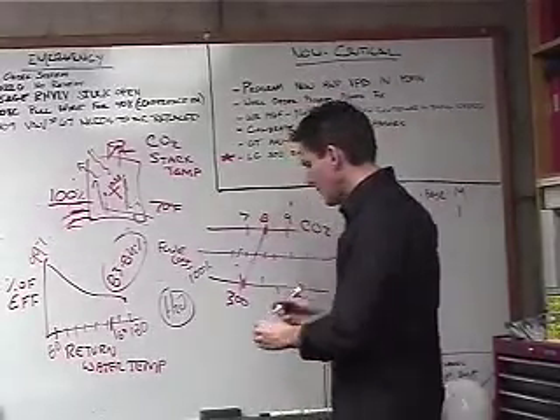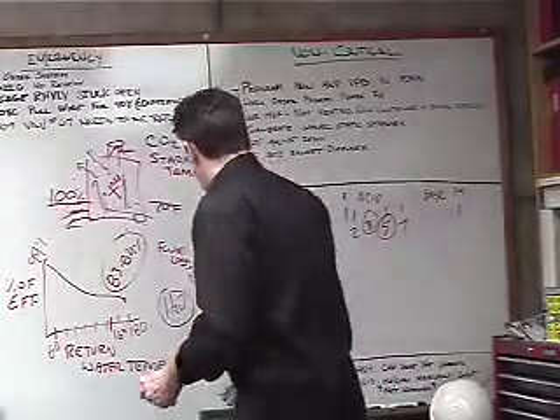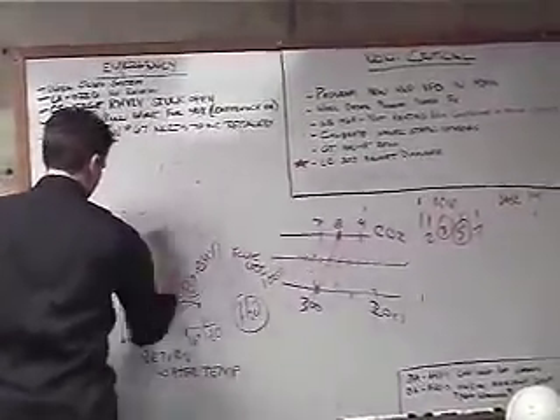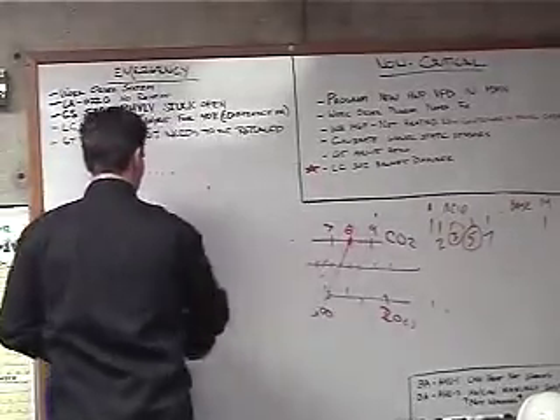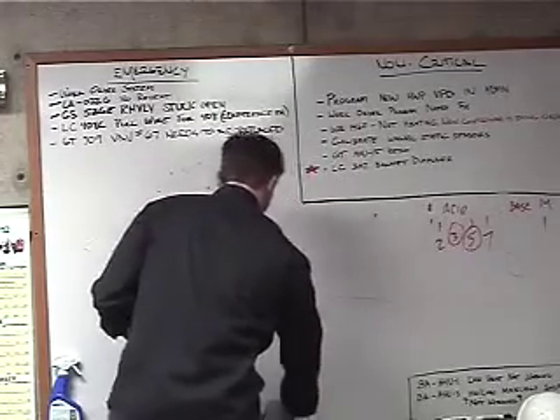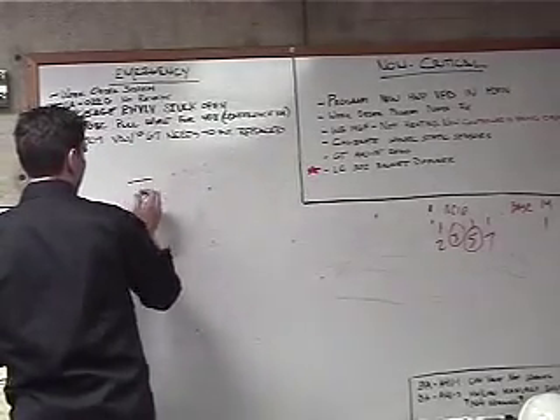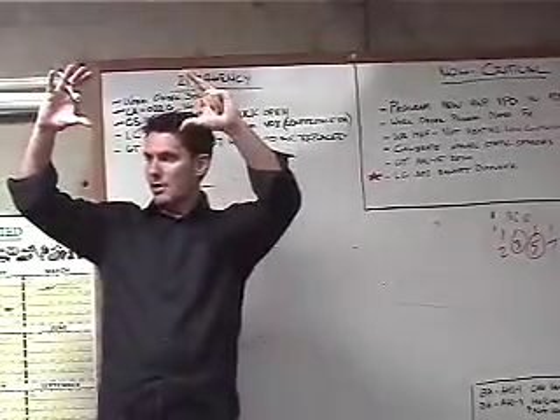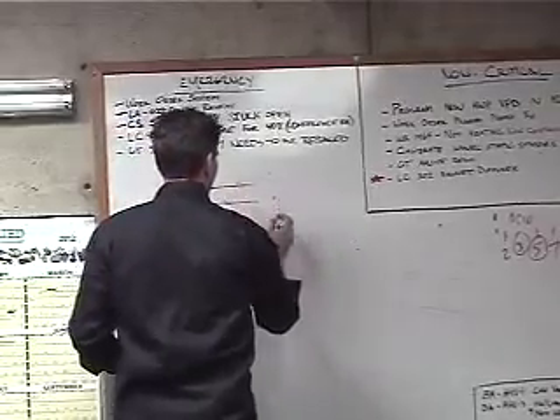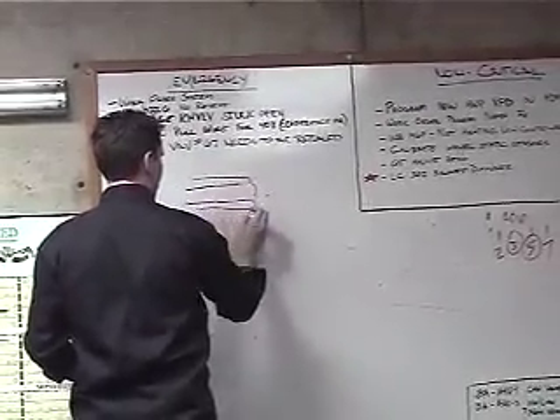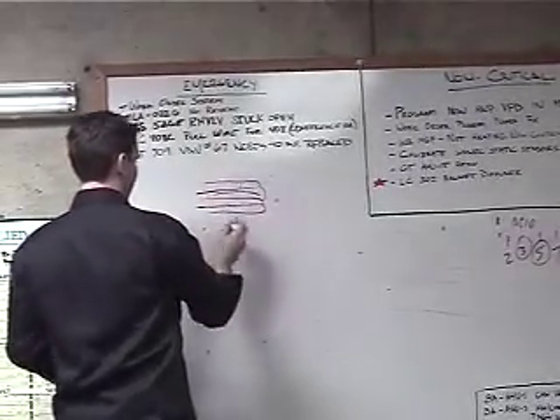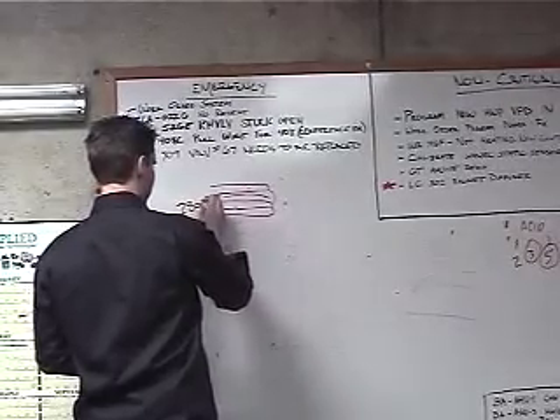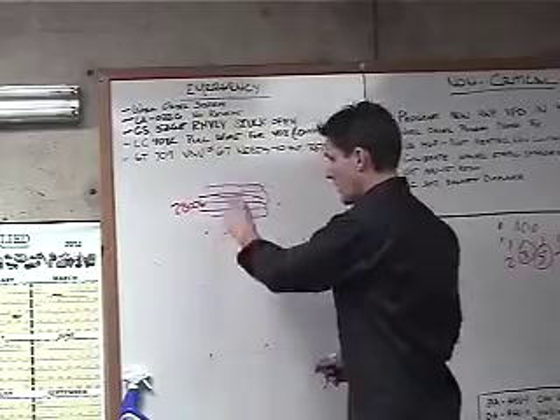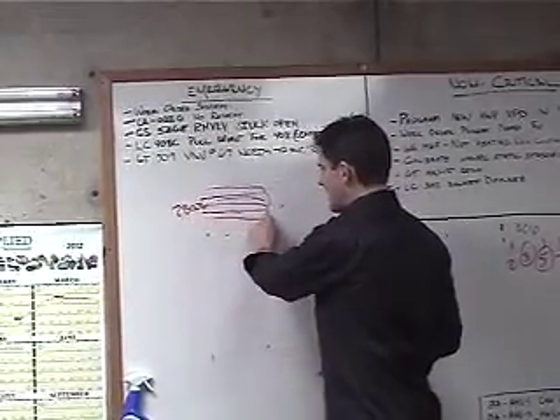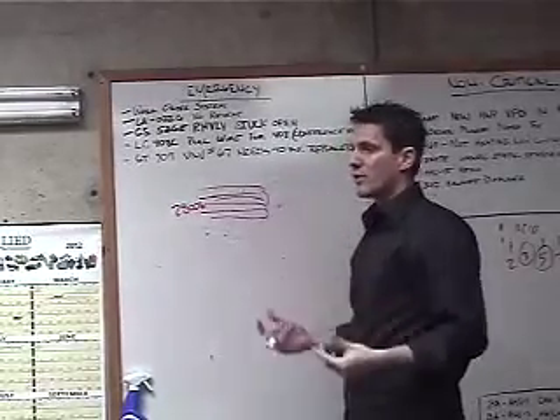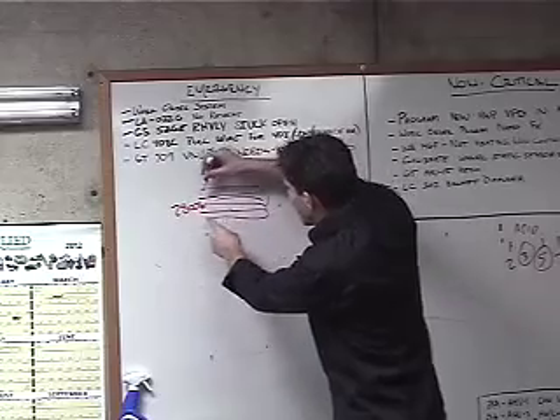So when we look at this boiler, these Fulton boilers that you have, you can tell I'm not a real great artist up here, but I'll try to draw what it does. When you look at the boiler, you'll notice that the burner is up towards the top. That burner shoots down a primary tube. Once it hits the end of this tube, it comes back in what we call tailpipes. These tailpipes run back to the front of the boiler. And so again, my flame temperature starts out around 2,800 degrees Fahrenheit. So we're really hot. This is what we try to target. Really hot flame. By the time it hits the end of these tubes, we're no longer a flame, we're just hot flue gases. So we're 300, 400, 500 degrees Fahrenheit. We hit the end of these tubes, we come back, we're still very hot.